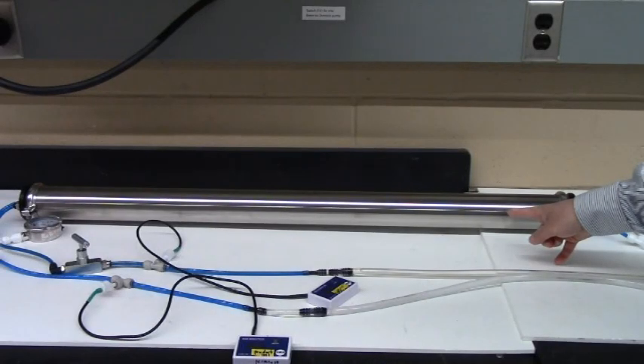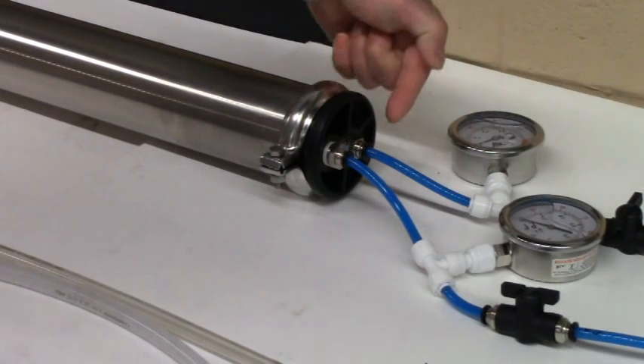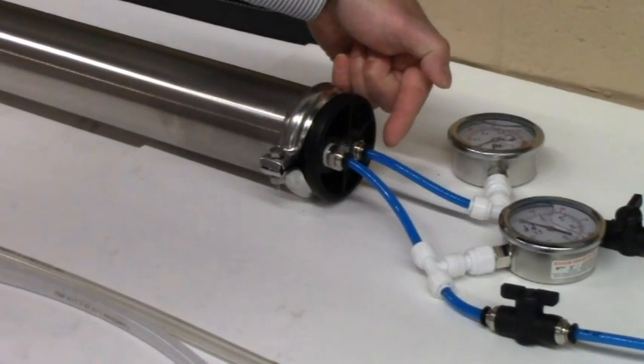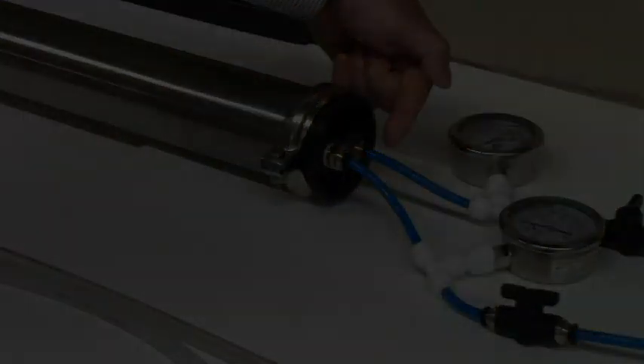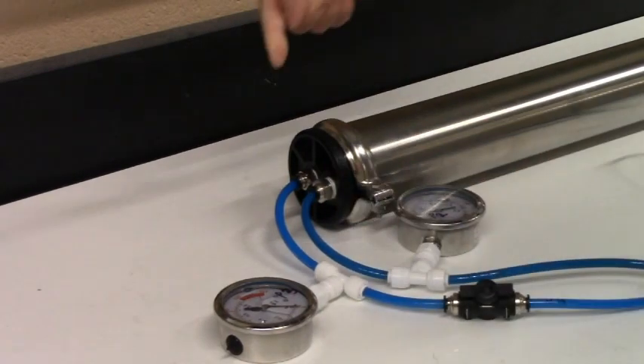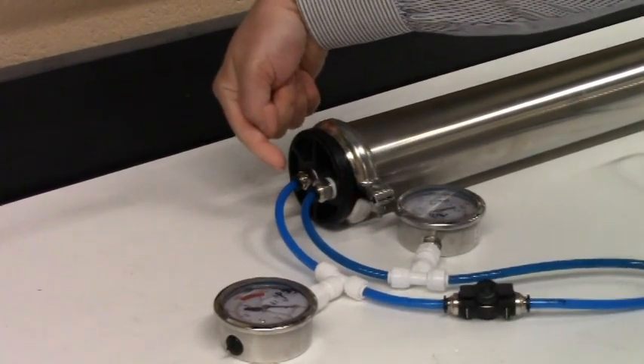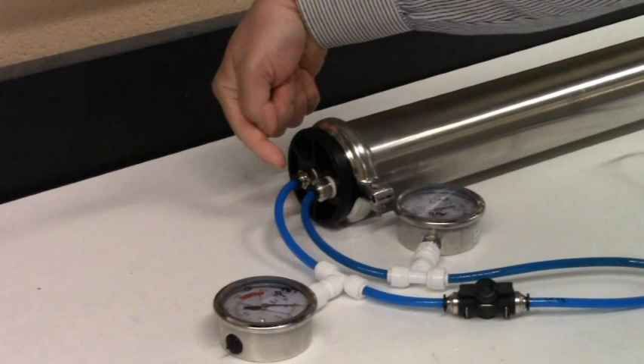The stainless steel column lying on the bench is a membrane housing. The RO membrane is inside the housing and cannot be seen. On the right end of the membrane housing, there is a filter inlet which is out of center, and a back flush inlet which is at the center of the cap. On the left end of the membrane housing, there is a reject outlet which is out of center, and a filtrate outlet at the center of the cap.